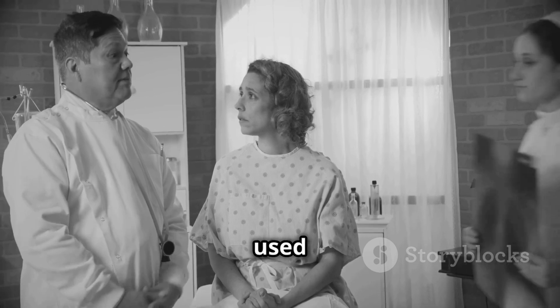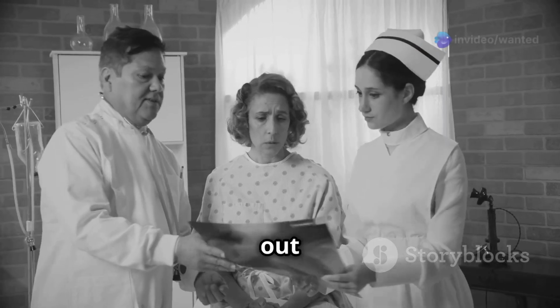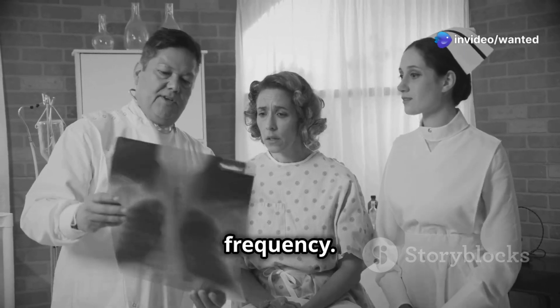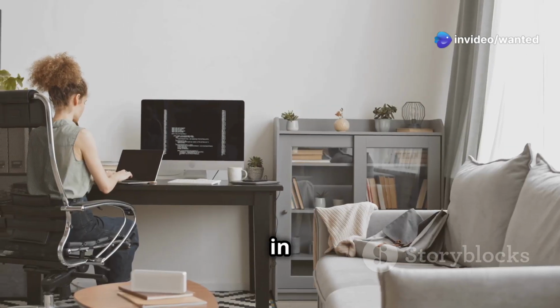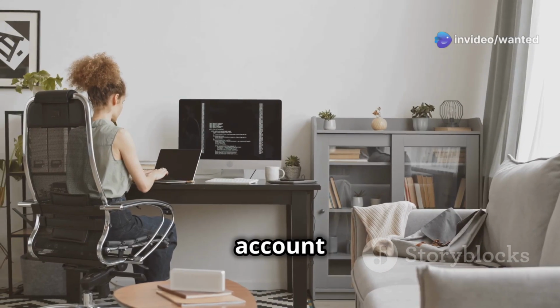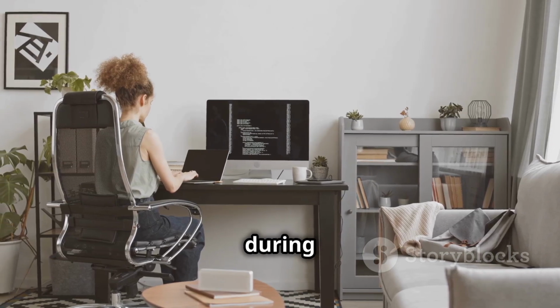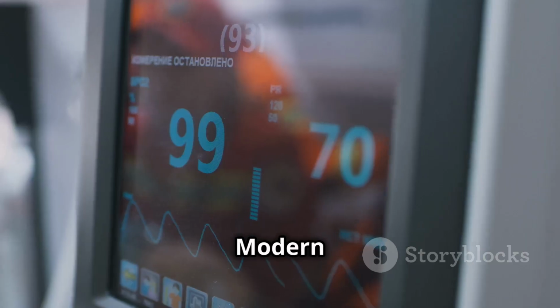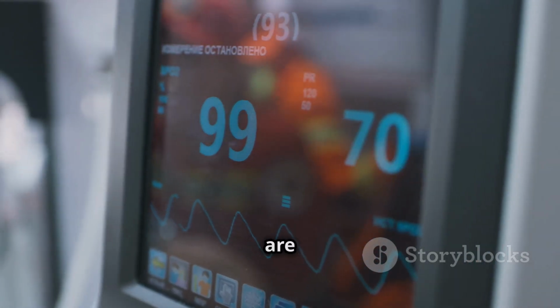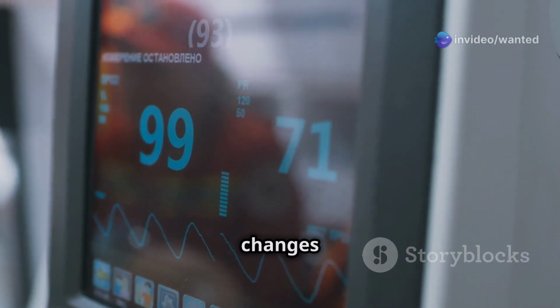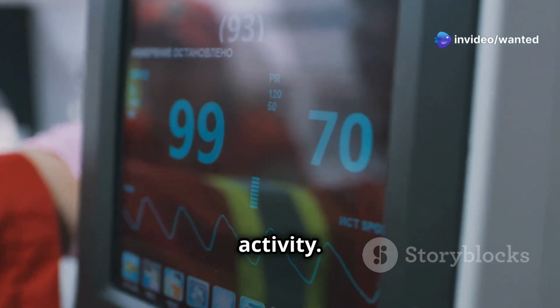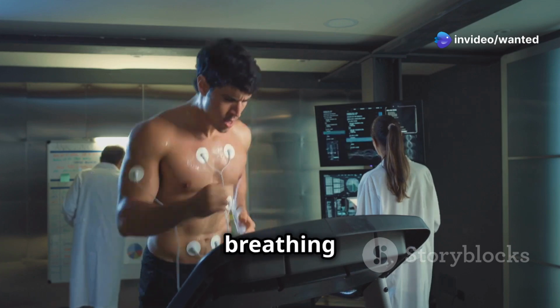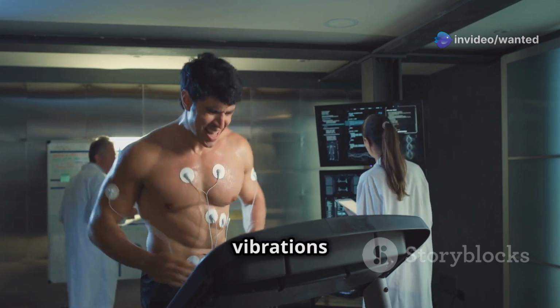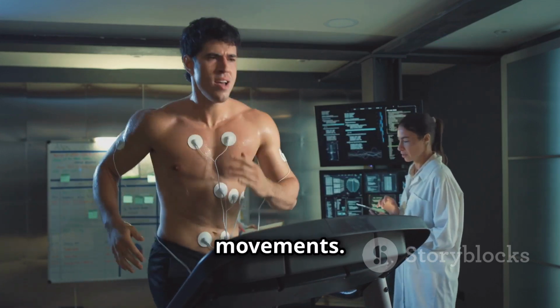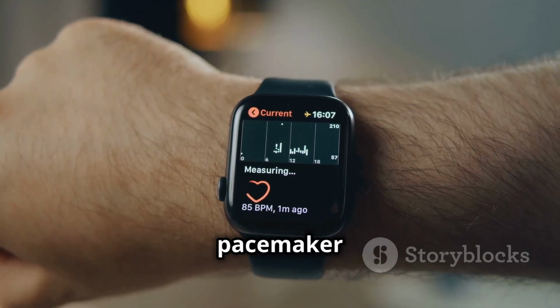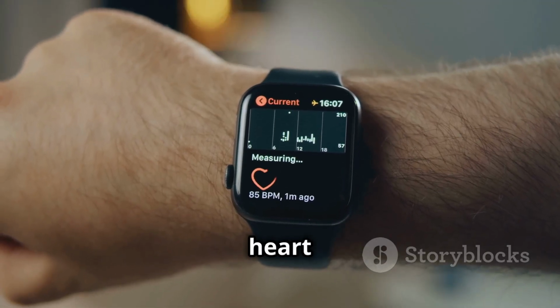Older pacemakers used to work at a fixed rate, sending out electrical impulses at a constant frequency. While this was effective in regulating the heartbeat, it didn't account for the body's changing demands during different activities. Modern pacemakers, on the other hand, are equipped with sensors that can detect changes in your body's activity. These sensors might monitor your breathing rate, body temperature, or even the vibrations caused by your movements. Based on this information, the pacemaker can automatically adjust the heart rate.